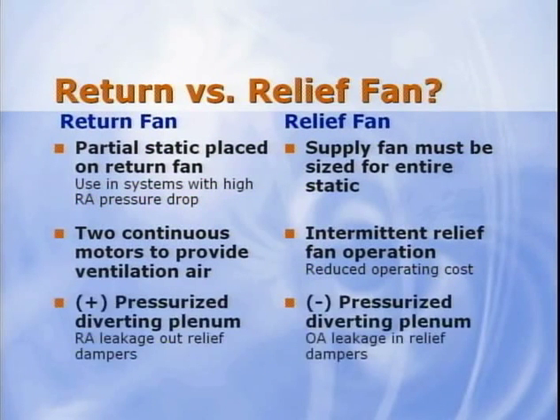Both systems should use low leak dampers. With a relief fan system, when the relief fan is off, the negative pressure diverting plenum may draw in outdoor air through the relief damper. With a return fan system, the opposite is true. The return fan pressurizes the diverting plenum, and conditioned air can leak out of the relief dampers. Low leak relief dampers help minimize both problems.